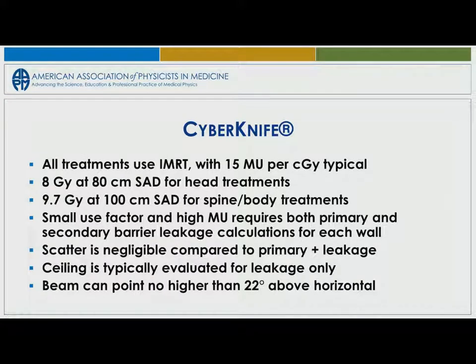All treatments are IMRT on a CyberKnife, and again, their ratio is 15 monitor units per centigray. So your leakage workload is really high on these units. Typically, we use a treatment of 8 gray for head treatments and 9.7 gray at 100 centimeters SAD for body or spine treatments. So you have a small use factor, you have a high monitor unit, and it affects both your primary and your secondary leakage workload calculations.